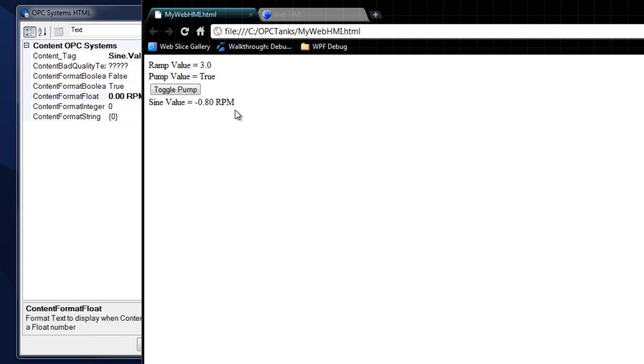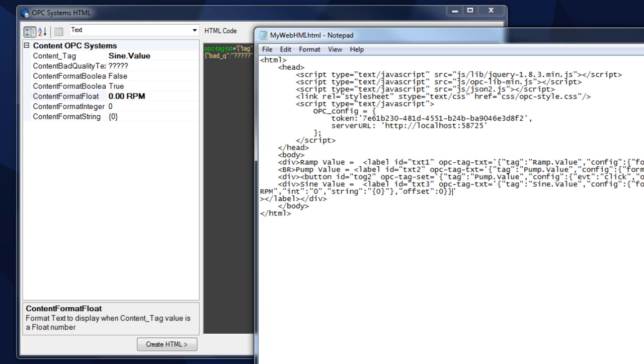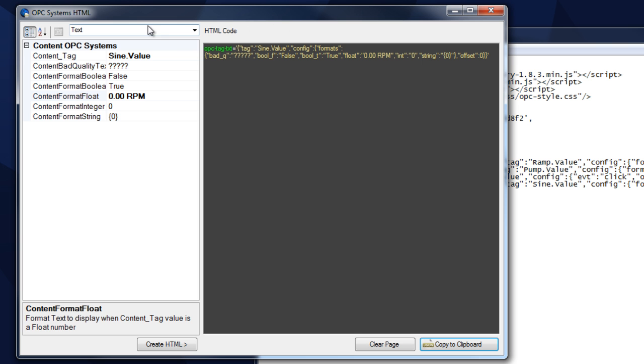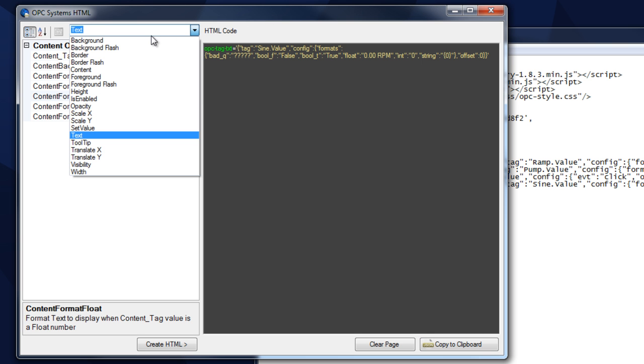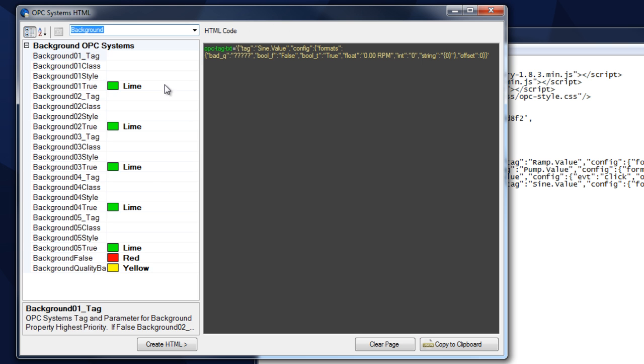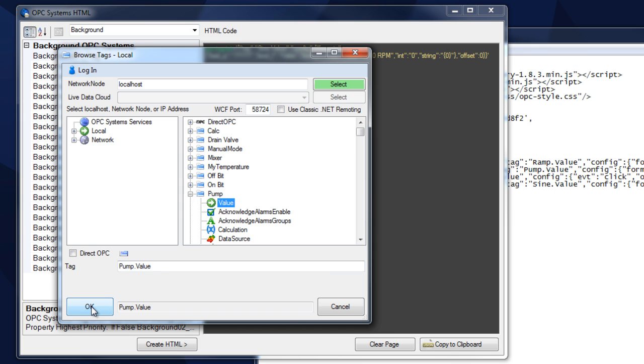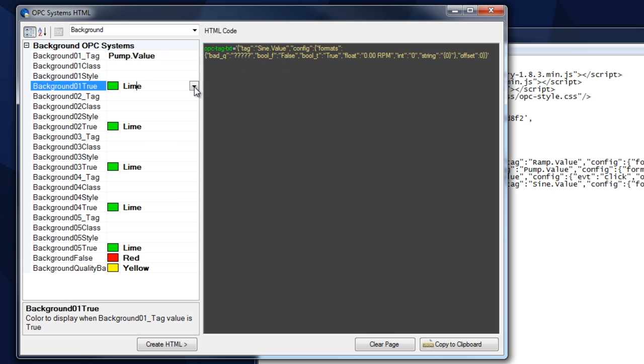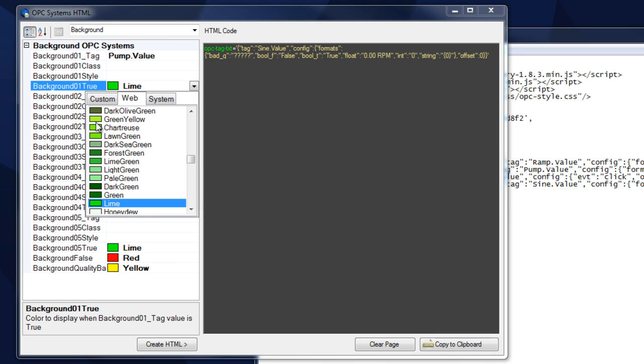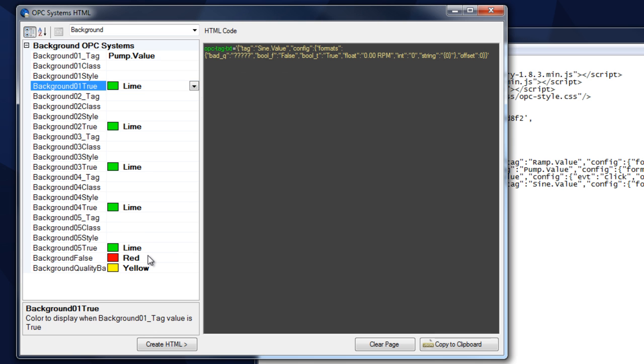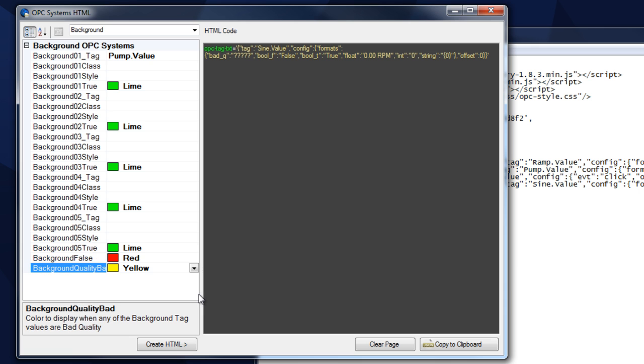Now let's add a few more properties to this particular label. We'll come back to our HTML wizard and select background. From here let's grab a tag to define our background. Select local and grab our pump value — this is a boolean point. Select OK. When that's true we'll have a lime green background, and when it's false it'll be red. Background quality will be yellow if it's bad quality.